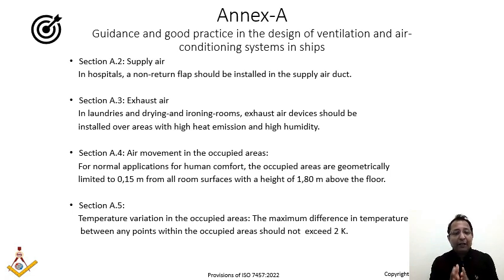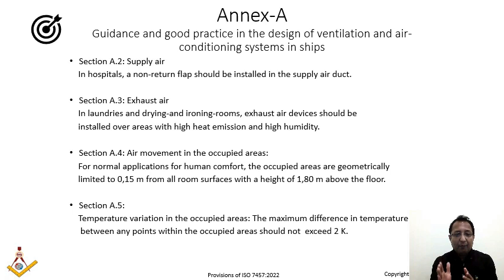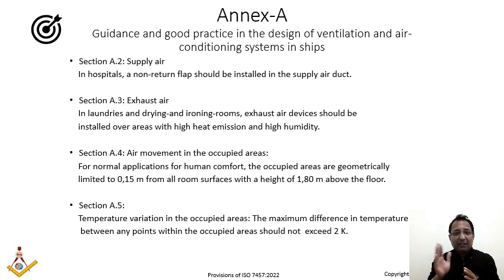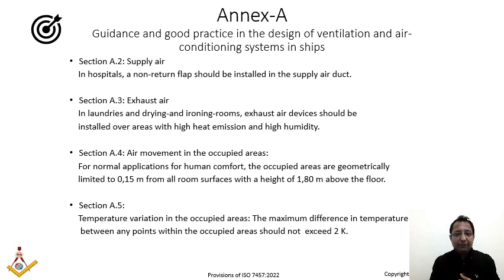Section A.4 states that for normal human comfort applications, the occupied zone is geometrically limited to 150 mm from all room surfaces, with a height of 1.8 m above the floor. This means the conditioned zone to be cooled extends 1.8 m high and starts 150 mm away from each wall — this is the zone your HVAC system must address.